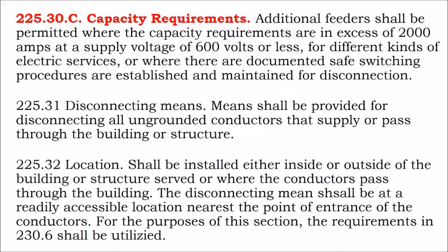Does there need to be a disconnect up on the rooftop? It says you need to have disconnecting means for disconnecting all ungrounded conductors that supply or pass through a building or structure. And actually, we get into rapid shutdown, and what we realize is that in the past, we've just taken the conductors from the array and fed them directly into the string inverter, and installers have been kind of getting around the spirit of this by staying outside the building, and they're not passing through the building.